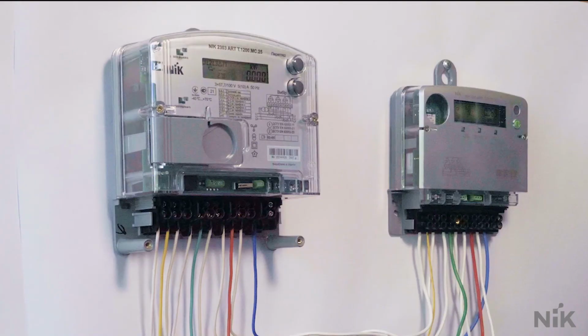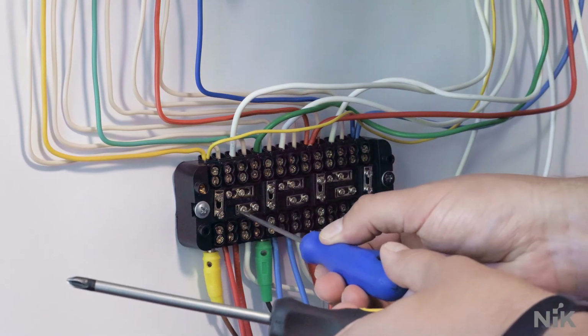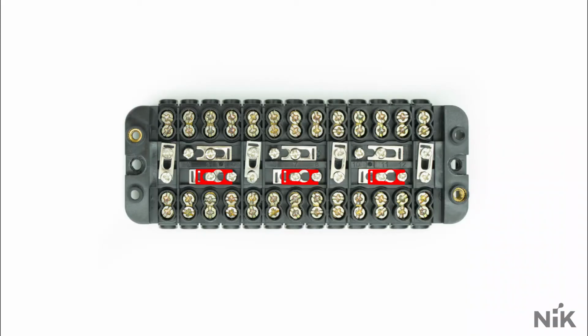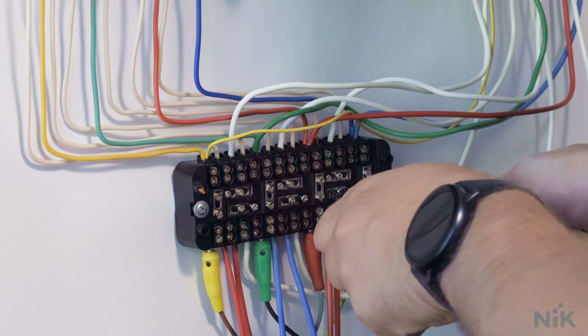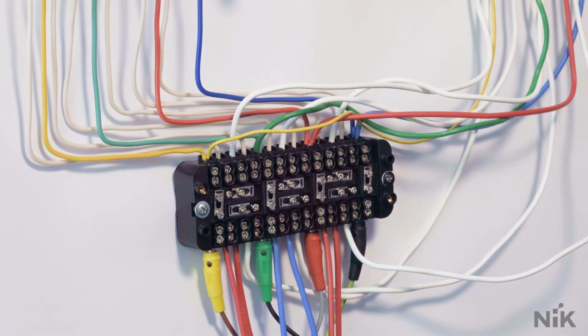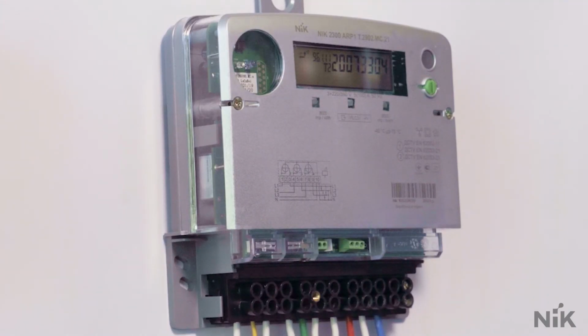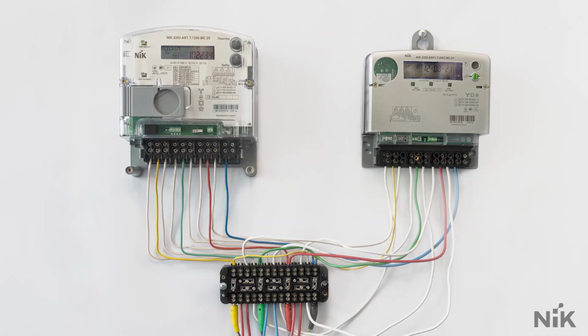After connection of this device, we push jumpers. This time we move lower jumpers, but we don't connect them as it was previously. Contrary to that, we disconnect them. All 3 jumpers are disconnected. Now let's look at the device. After disconnection of lower jumpers, we can see that load is flowing through second device. In this case, the first and second devices are connected into the same circuit. Using this method, we can compare the data of the first and second device, or we can check accuracy of the second device under existing load.